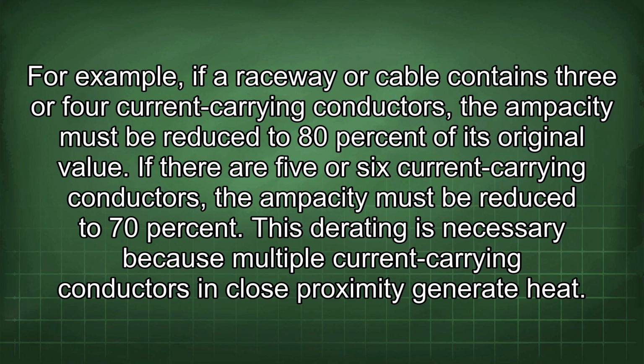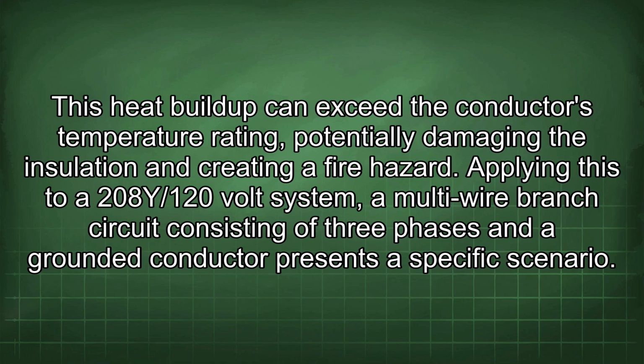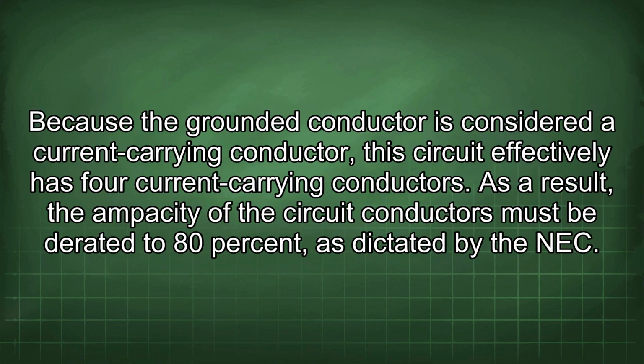This derating is necessary because multiple current-carrying conductors in close proximity generate heat. This heat buildup can exceed the conductor's temperature rating, potentially damaging the insulation and creating a fire hazard. Applying this to a 208Y/120 volt system, a multi-wire branch circuit consisting of 3 phases and a grounded conductor presents a specific scenario. Because the grounded conductor is considered a current-carrying conductor, this circuit effectively has 4 current-carrying conductors. As a result, the ampacity of the circuit conductors must be derated to 80%, as dictated by the NEC.